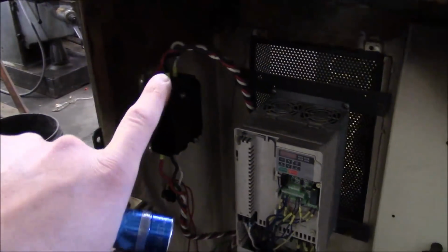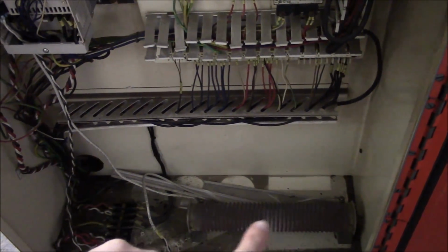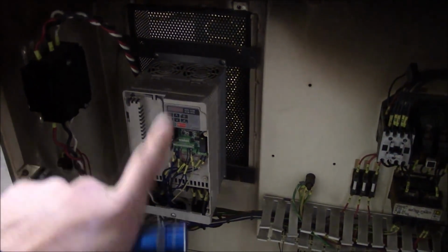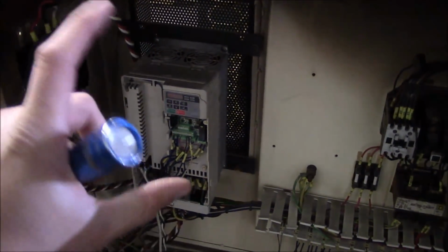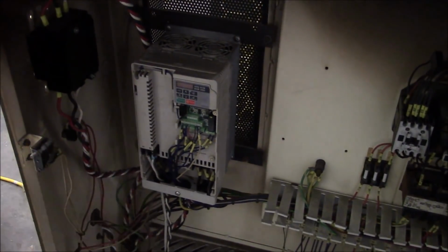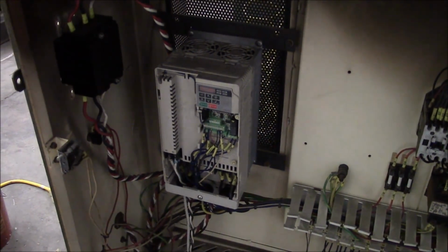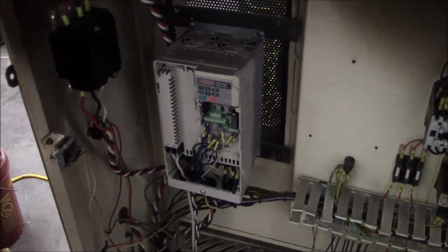Looks like this is not the original breaker, so it probably destroyed that when it happened. And this is not the original brake resistor, so obviously they just replaced that with something else. This is kind of comically large. And you can see the wire loom's all damaged here. So it must have been quite an event. At any rate, they put a new Yaskawa spindle drive in, and there's nothing wrong with that. This drive probably has better performance characteristics than the old drive anyway.